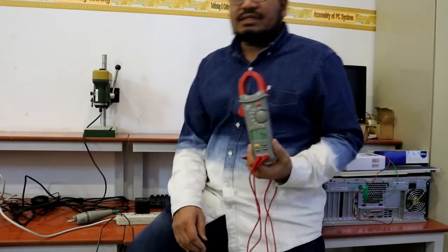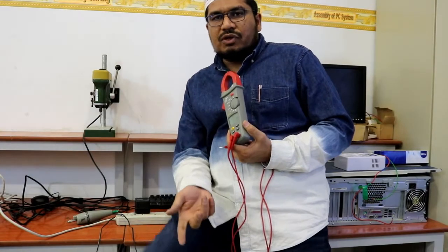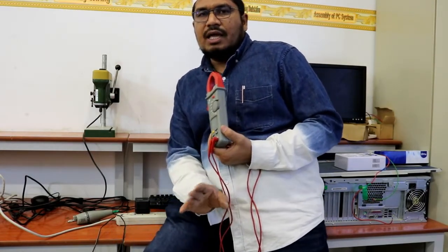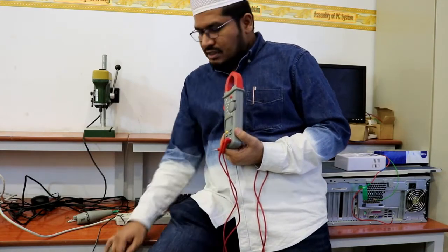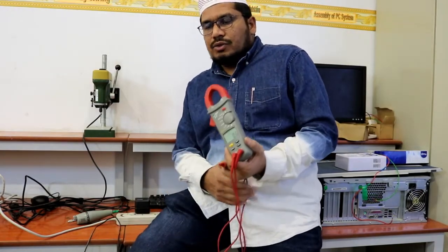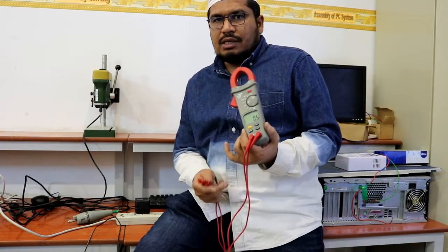So for any supply, there will be a plus or minus 5% tolerance. So 220 volts, plus or minus 5% tolerance, it is permissible for any country supply voltage. So we are getting supply from this ECO company, the electricity company. So what it is showing is 229.